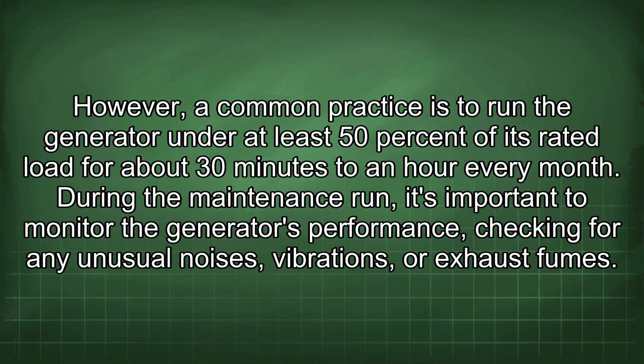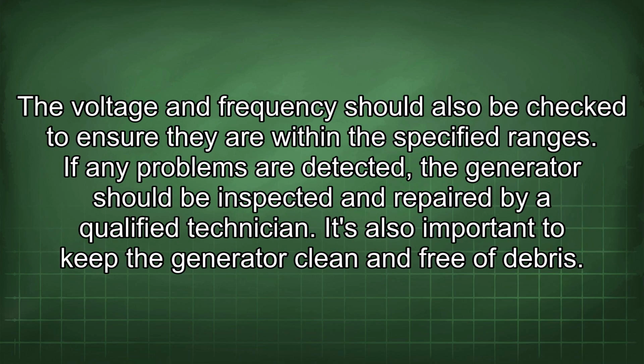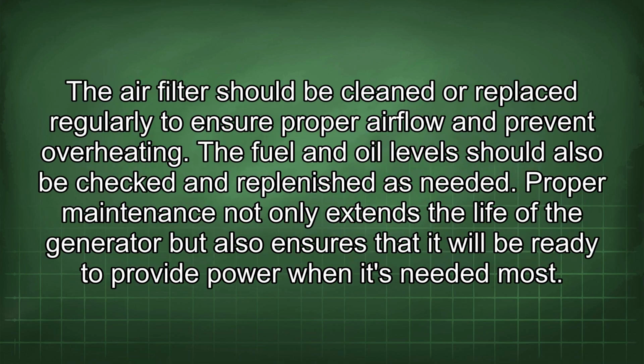During the maintenance run, it's important to monitor the generator's performance, checking for any unusual noises, vibrations, or exhaust fumes. The voltage and frequency should also be checked to ensure they are within the specified ranges. If any problems are detected, the generator should be inspected and repaired by a qualified technician. It's also important to keep the generator clean and free of debris. The air filter should be cleaned or replaced regularly to ensure proper airflow and prevent overheating. Fuel and oil levels should also be checked and replenished as needed. Proper maintenance not only extends the life of the generator but also ensures that it will be ready to provide power when it's needed most.